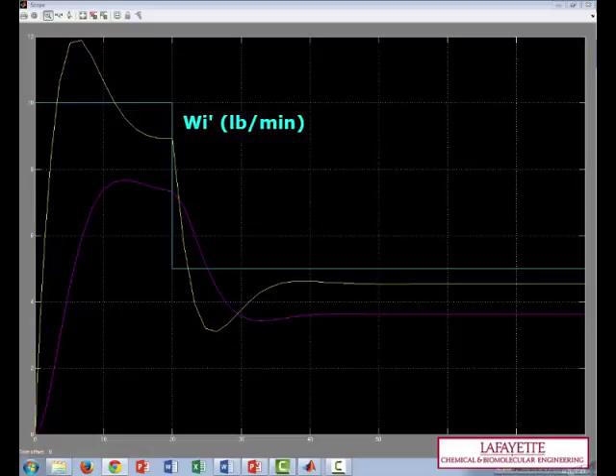An important thing to note here is the units of the x and y axes. The x-axis is time. The y-axis is pounds per minute for the flow rate, but it's psig for the tank pressures. As inlet flow rate increases, the pressure in both tanks increases. Both tank pressures have stable but oscillatory responses to the change in flow rate. The pressure in the first tank increases more, and at a faster rate. And the pressure in the first tank also oscillates more when there is a flow rate change. But eventually, the pressures in both tanks converge to a final steady state value.